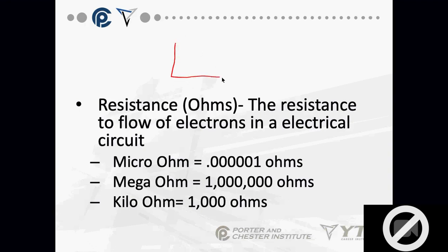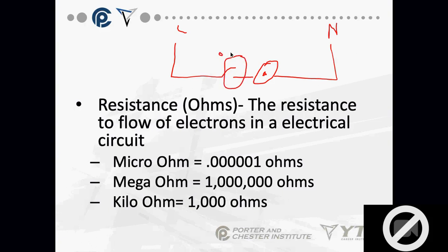Resistance is the opposition to the flow of electrons in an electrical circuit. Looking at my circuit with a switch — if the switch is open, what's the resistance? An open switch has infinite resistance. If I disconnect power and take an ohm reading across an open switch, the meter will display OL, which stands for open line, open load, or infinite.